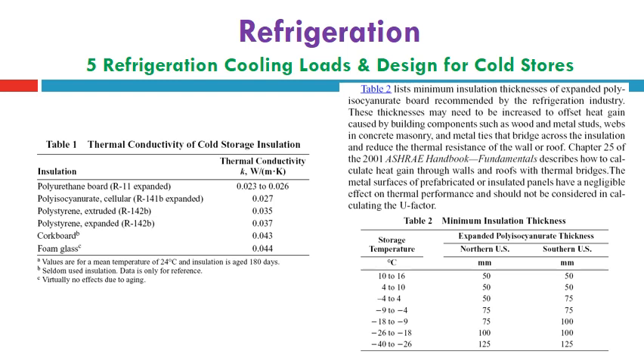So we can generate the value of X over K from Table 1 and Table 2. Table 1 presents the K values of different materials, and Table 2 presents the commonly used thickness, which can be used in our calculation when estimating the overall heat transfer coefficient U, which is based on X, the wall thickness, and K, the thermal conductivity of the used material.